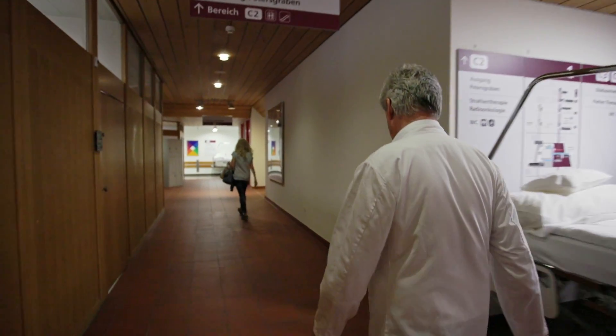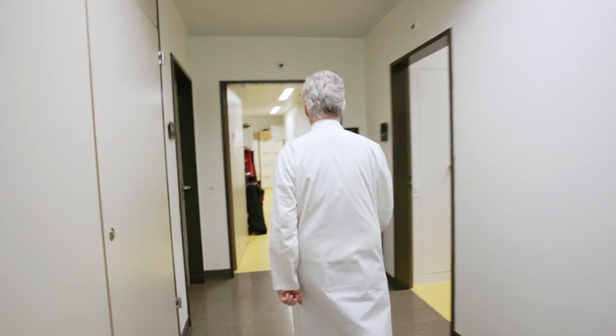I think as a good first step, and everyone can do that, is turn off your systems whenever reasonable — meaning during the weekends or overnight — and you can cut back on the energy consumption and the carbon footprint by roughly 30% without doing any harm.